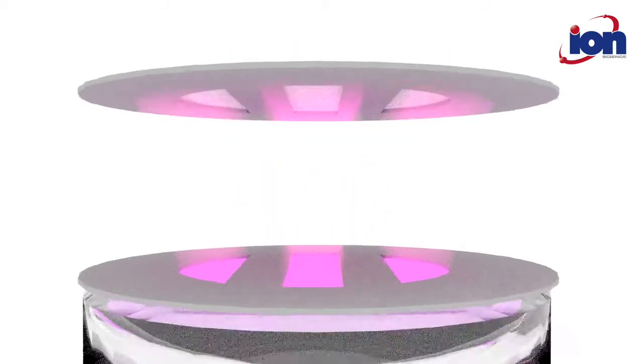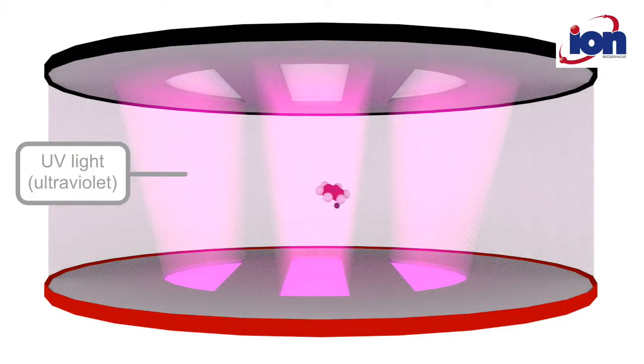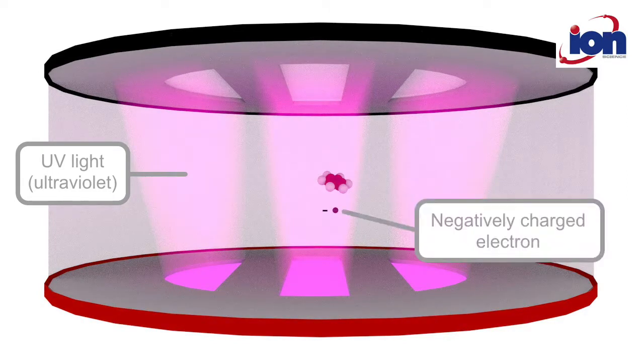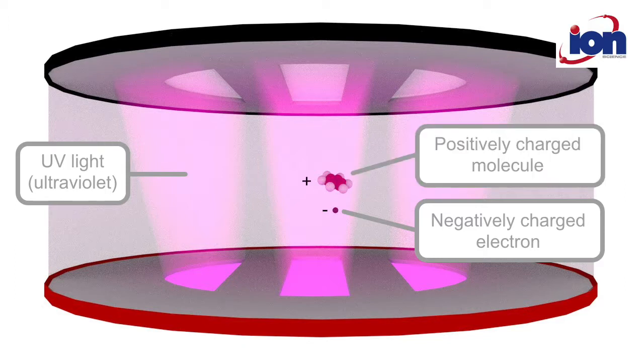When VOC gas enters the detection chamber, ultraviolet light energizes the molecules, releasing negatively charged electrons. The VOC molecules therefore become positively charged.